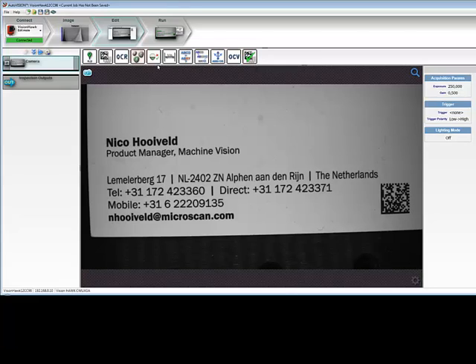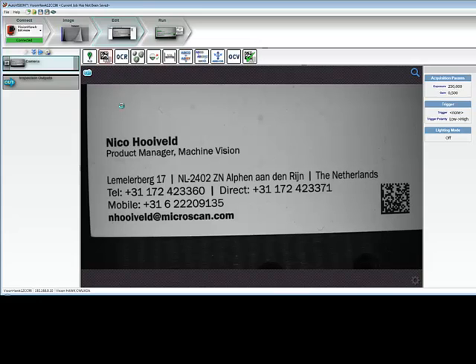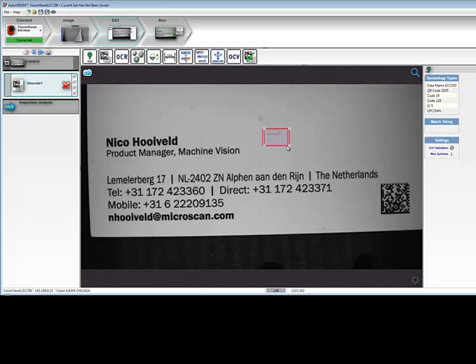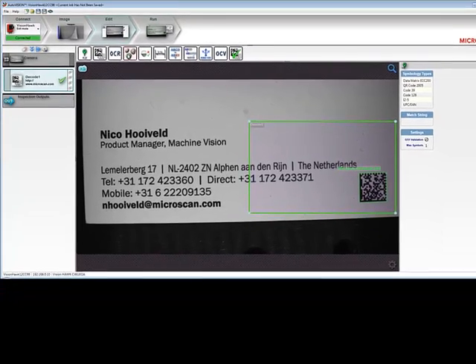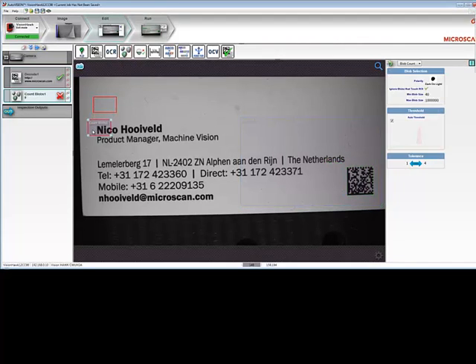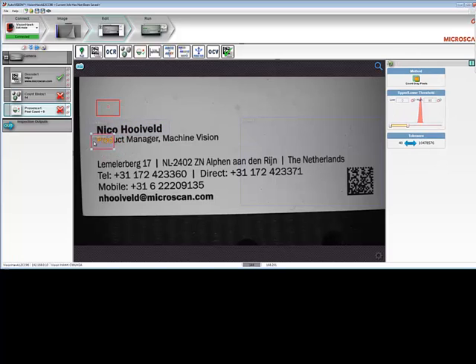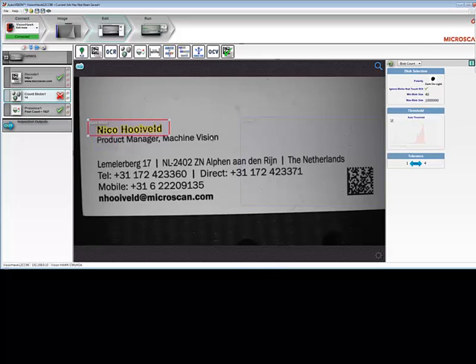The second step in creating a job is very easy. You simply click on a tool and set the region of interest to see the specific feature that you're looking for. You can easily combine tools. For example, you may want to count objects and check presence and absence to ensure that the required elements are there. You can set tool parameters and pass/fail levels by clicking on your tools. In this case, we're counting characters, so we can set a maximum number of characters here.